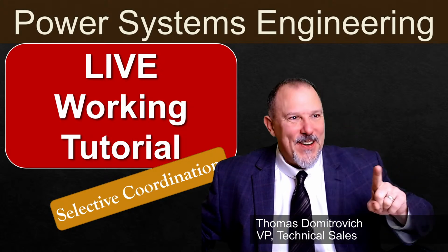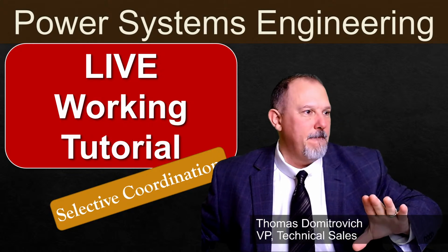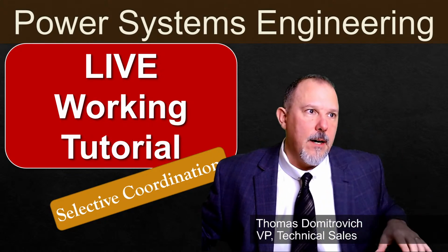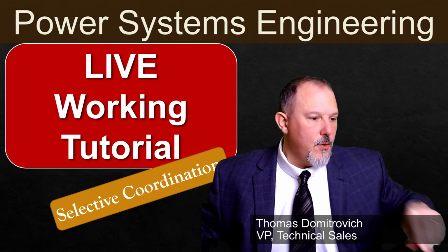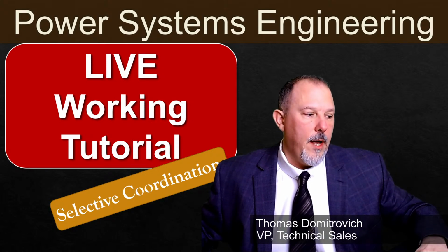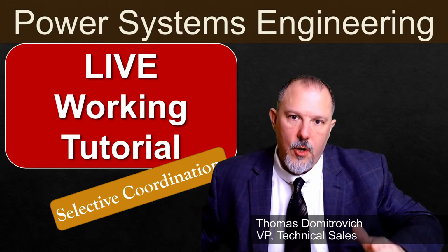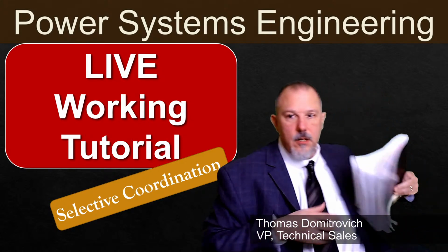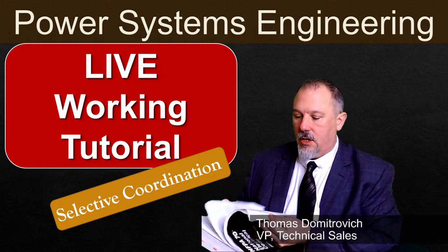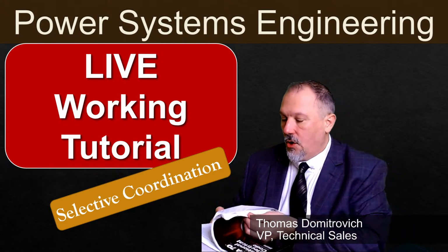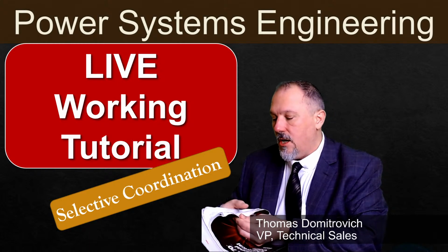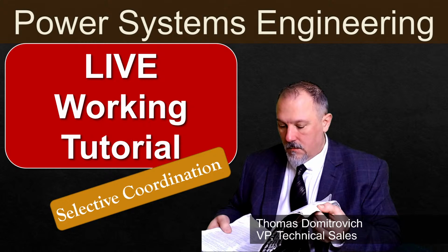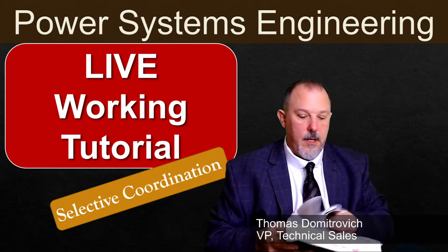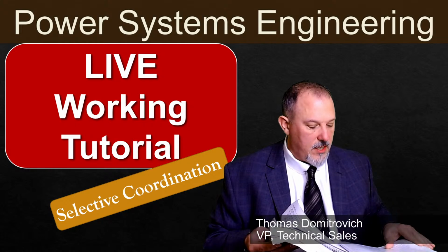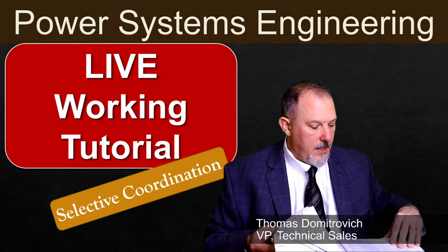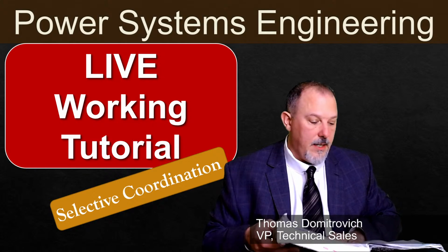Okay, but that's not what we're here to talk about. We're here to talk selective coordination. Now, selective coordination is a requirement in the National Electrical Code. Let's take a look at the definition in the National Electrical Code. I'm going to go to Article 100, and you have to look under coordination, selective. If you're in the 20 code, don't go to the medium voltage side. You've got to go to the low voltage side and look for the C's. And I'm going to read to you what it says.